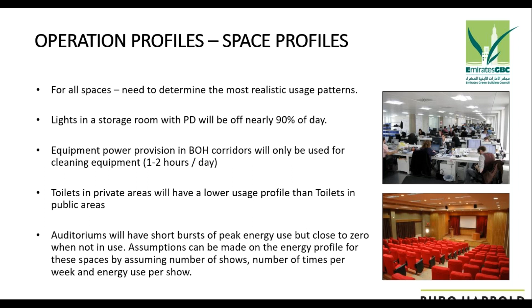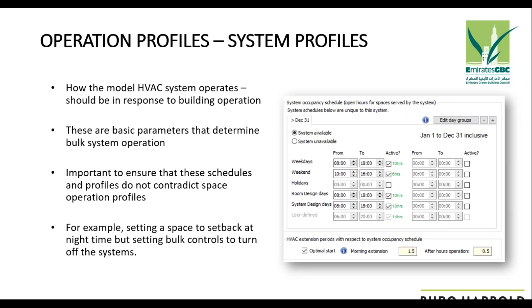System profiles, I'll touch upon this quickly because it's mainly about setting the bulk system operation - is it on, is it off, when is it on from, when is it off from. The only thing to remember is that it should not clash with the space profiles. So if you've asked your space to set back at night from 24 to 27 degrees, don't tell the system to switch off - that causes problems.